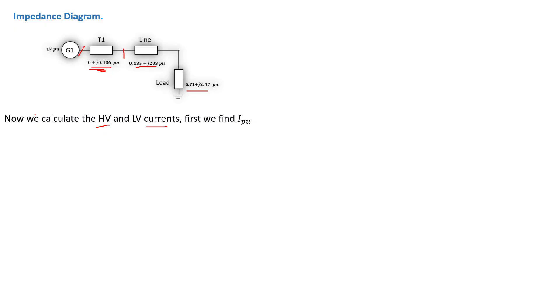We need to find the current flowing on the high-voltage side and the low-voltage side. Remember it's a series circuit, but because there is a transformer, the current on the high-voltage side is not the same as on the low-voltage side — this is the primary current and this is the secondary current. Before we do that, we need to find I per unit for the entire system. The formula is: I per unit equals one divided by Z per unit total. The '1' is actually V per unit, which is always equal to one in a balanced normal system.